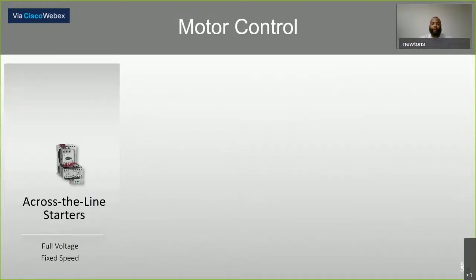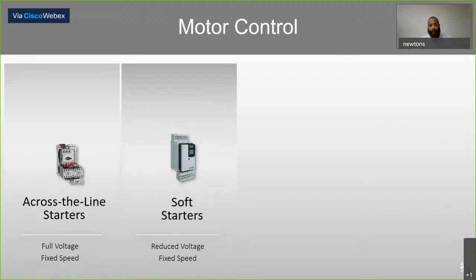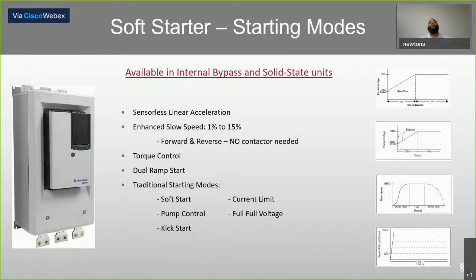The second type of technology that is used in motor control, a step above the across the line starter, will be your soft starter. Your soft starter gives you a combination of basically a starter and some of the capabilities of a VFD, or variable frequency drive, which essentially allows you to control the ramp, instead of going from 0 to full speed instantaneously. It's going to be some time between 0 and 60, but as fast as possible, all right?